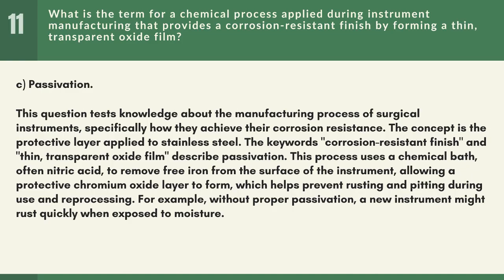This process uses a chemical bath, often nitric acid, to remove free iron from the surface of the instrument, allowing a protective chromium oxide layer to form, which helps prevent rusting and pitting during use and reprocessing. For example, without proper passivation, a new instrument might rust quickly when exposed to moisture.